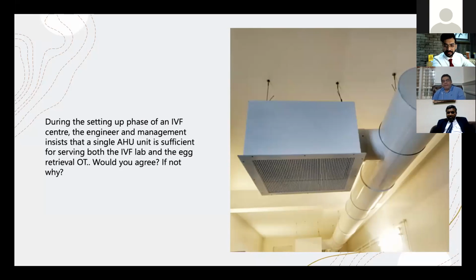At the end, I would think that these are good practice points. But when you have to measure success between a laboratory which has these provisions and the majority of laboratories which don't, if the KPIs are being achieved, if I can say that I have a very good percentage of expanded blastocysts and implantation rates, and my pregnancy loss rate is equivalent to a laboratory in Norway or in Scandinavia, where the outdoor air quality is perhaps better than the air inside our laboratories, then that's a very strong argument. Okay, Gaurav, here I would like to come in and comment on it. See, around 15 to 20 years ago, we also used to work without any AHU, and we used to get good pregnancy rates, depending upon whatever was persistent at that time.